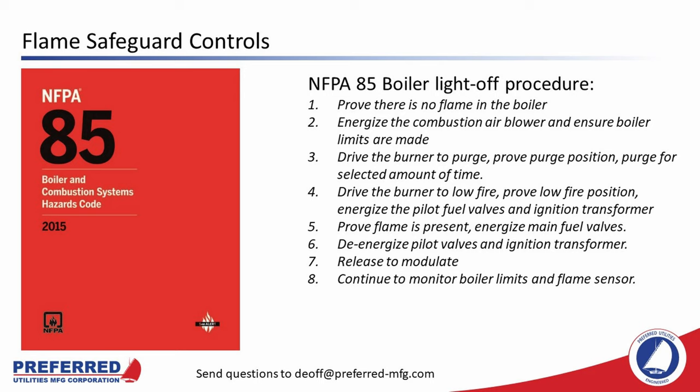The NFPA boiler light-off procedure is as follows. First, you prove that there is no flame in the boiler using an input from the flame scanner. Second, you energize the combustion air blower and ensure boiler limits are made. Then the flame safeguard controller will drive the burner to purge, prove purge position with either a limit switch or feedback pots, and then purge for the selected amount of time — usually five air volume changes, sometimes as many as eight to ten depending on the type of boiler.